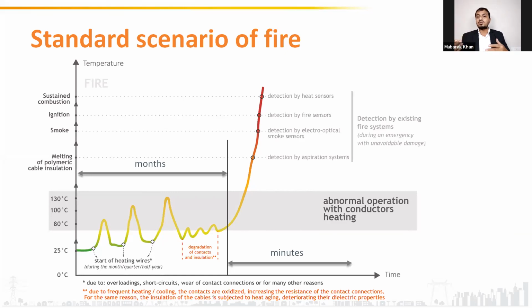Now, what is the abnormal zone? As I explained before, the normal zone is between 25 to 70 degrees Celsius. And any abnormality or the discoloration of the PVC insulation starts after 180 degrees Celsius. So we can say that between 80 to 180 degrees Celsius, it is an abnormal zone. To be on the safe side, we take the lower 50% of the band. So it is between 80 to 130 degrees Celsius, right? If we are able to detect the abnormality between 80 to 130 degrees Celsius, then we'll be able to save any fire or failure scenario by getting information well in advance.